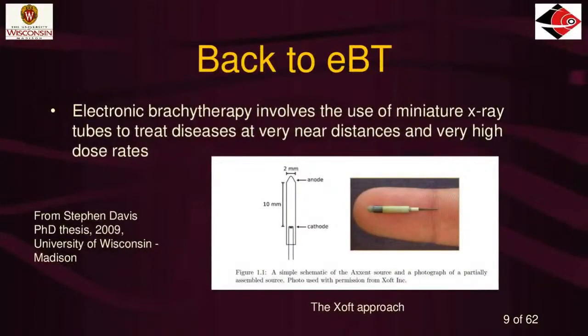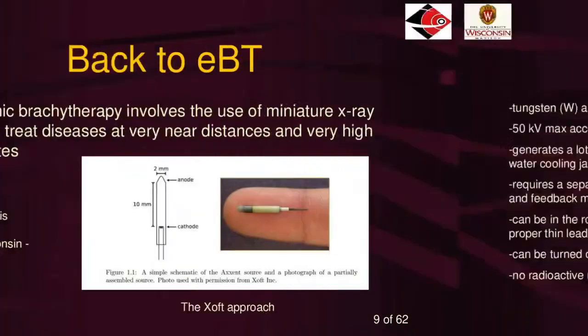Back to electronic brachytherapy dosimetry. Electronic brachytherapy involves the use of a miniature X-ray tube, not a radionuclide. We treat diseases with this at very near distances and very high dose rates. An example is the Xoft Axxent miniature X-ray tube — a fantastic piece of engineering you can see sitting on someone's finger. It has a cathode on one side and a tungsten anode on the other, and you apply 50 kilovolts as the max energy. The electrons go down a tiny accelerator tube, hit the target, and create Bremsstrahlung radiation that can be put inside a patient or used to treat skin. They actually glow blue when you turn them on.